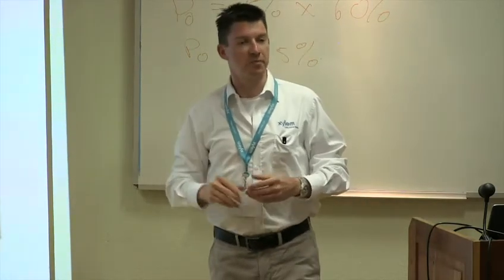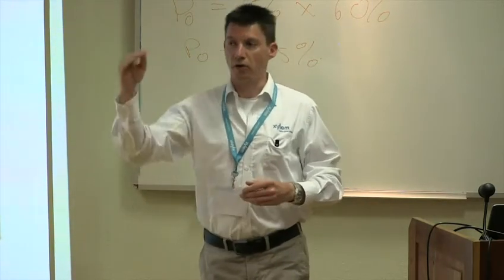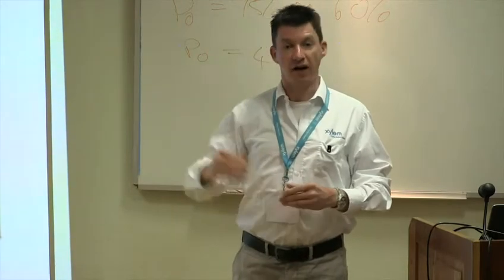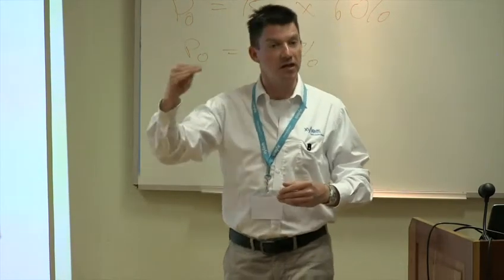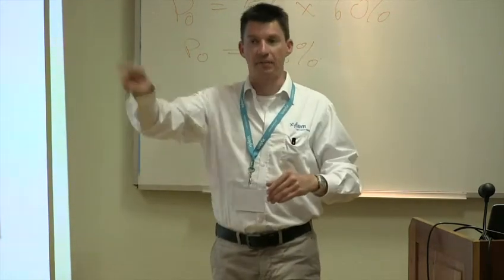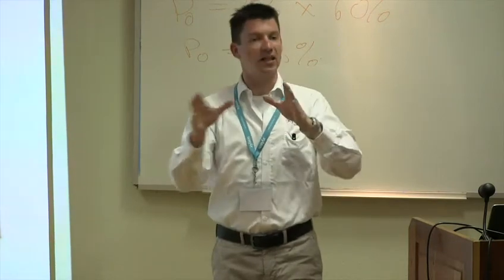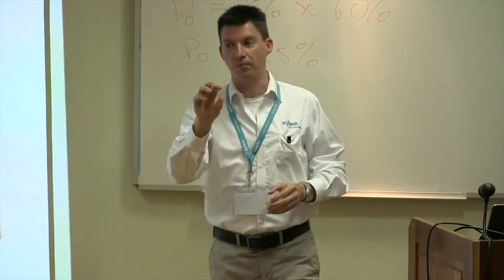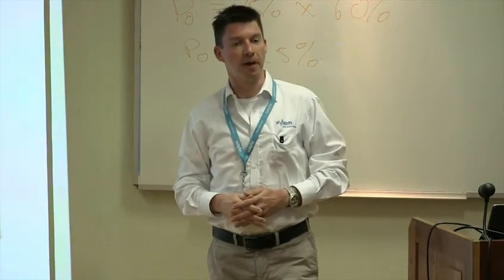Now I reduce my speed by 1 hertz - oh, it's 2.9 kilowatt hours, that's fine, I go down another hertz. So it goes down, down, down until it gets the minimum, and then it sees, okay, that's my best point, the best point I can reach, and there it runs my pump.